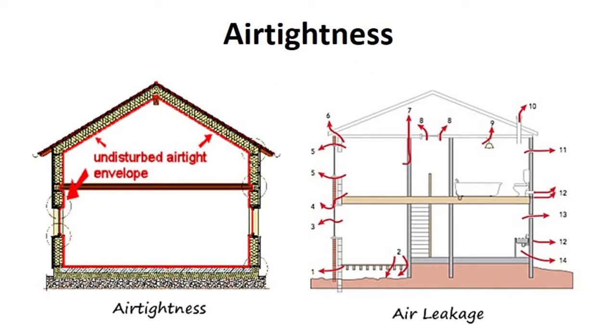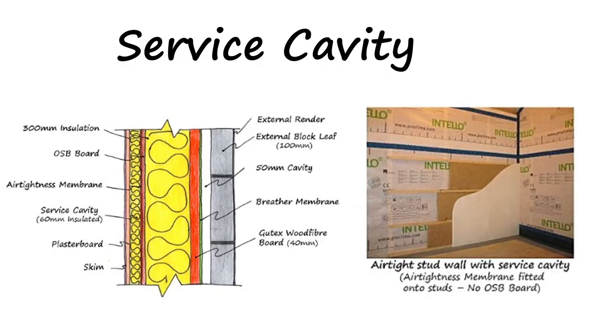The next aspect which is vitally important to passive house construction is air tightness. Air tightness is the control of air flow within a building, meaning there is no unexpected air leakage. Air tightness can be achieved by having an undisturbed air tightness barrier on the internal envelope. There are several methods of creating an air tightness barrier, and the approach chosen often depends on the level of air tightness you are trying to achieve. In passive house construction, an air tightness level of 0.6 air changes per hour has to be achieved, and a service cavity with an air tightness membrane is a common approach.